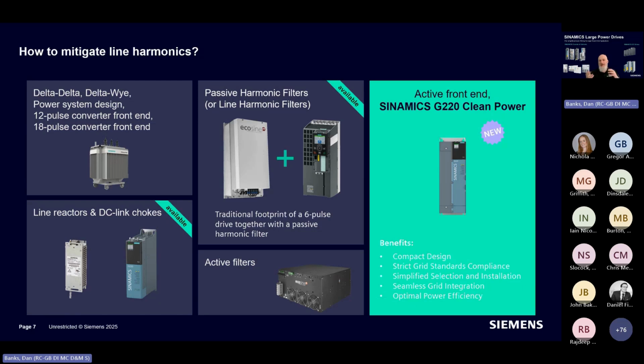The next step is to go to a passive filter. This is a tuned circuit. Essentially, it tunes into that frequency of noise. It cuts it out, takes it away. Not well accepted in the UK, I'd say. There are challenges with them, because they're tuned circuits, in their tendency to pick up other noise around them, soak it up, maybe get into a resonance with the circuit they're connected to, and they have a tendency to overheat and cause challenges if they're not designed correctly in the space.